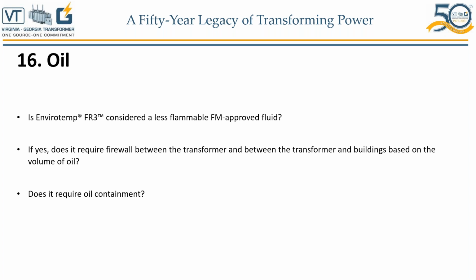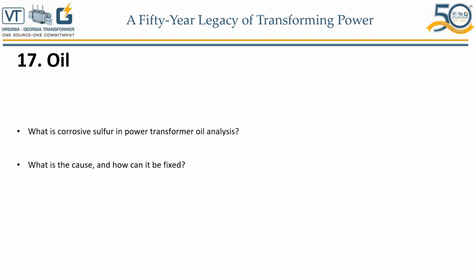Does it require oil containment? Well, once again, I'm not a substation guy, but just because the oil is biodegradable doesn't mean that you don't need to contain it. If I was designing that substation, I would prefer to still have oil containment regardless of what type of oil I am using in my transformer. What is corrosive sulfur? Good question. I'm going to do a little check. I think this is the last slide. Yep, that's the last slide. So I'll take my time and answer that.